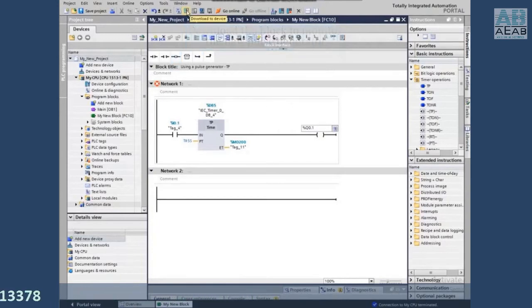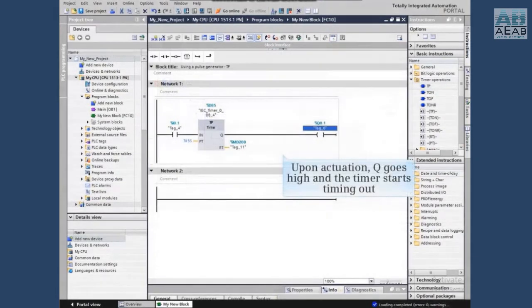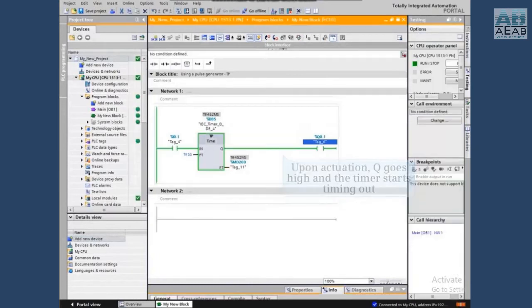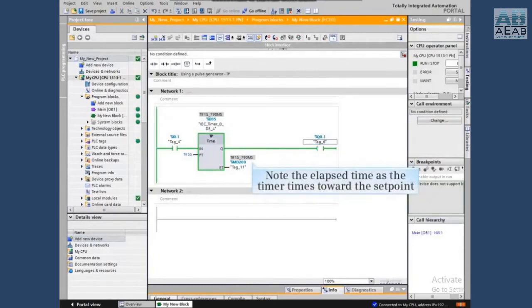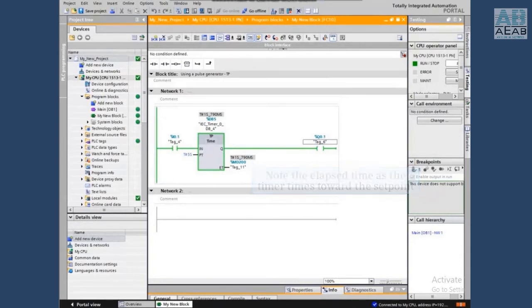We will now download the block to monitor the new pulse generator, and click the eyeglass icon to monitor the block. Upon actuation, Q goes high and the timer starts timing out as shown in the ET. The ET output shows the elapsed time since the timer was actuated.